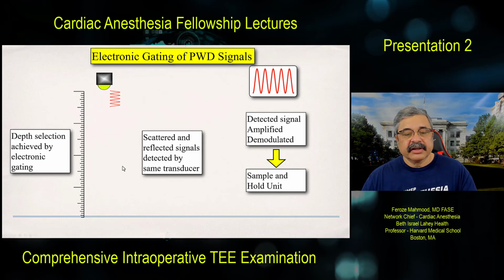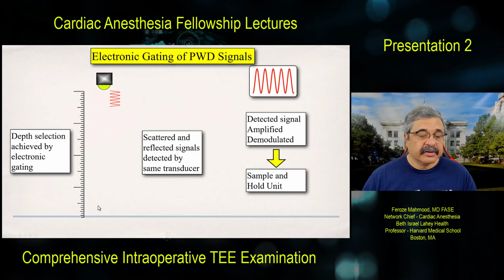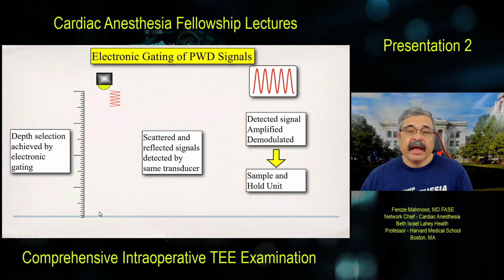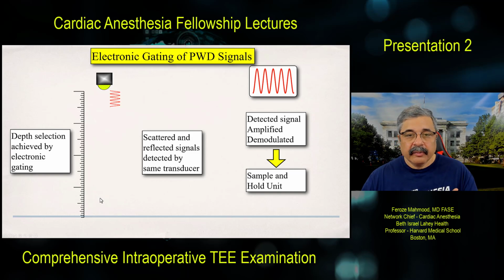So scattered signals are detected by the same transducer, because now you are sending out a signal, waiting, and then there's a go-return time involved in assessment of velocity, and therefore there is the likelihood of aliasing, which means if the object of interest at the location of the sample volume, the RBCs, are moving faster than you can analyze them, then you wouldn't be able to tell whether they're moving away or towards the transducer, and that's called aliasing. And that's the reason we cannot use pulse wave Doppler at certain locations, because the velocity of the RBCs is way more than what we can detect.